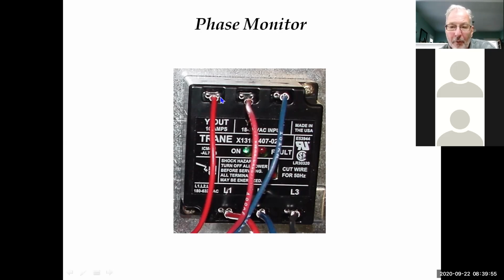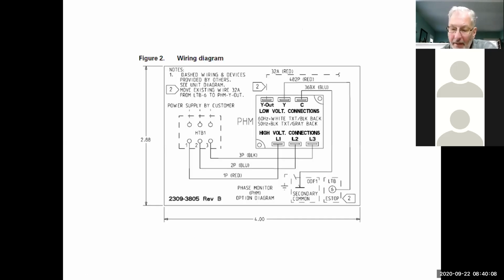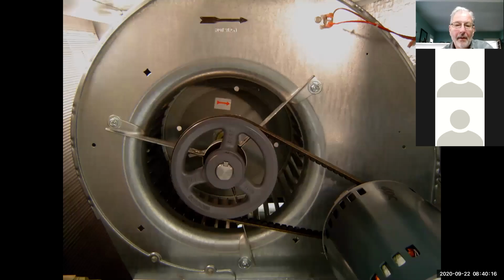Make sure you're getting 24 volts on this Y out. Here's your power, line 1, line 2, line 3. It's just monitoring power. Make sure you've got all three phases. Make sure they're phased properly. This is the internal connection to it. And again, we feed that by itself. We feed it from a separate circuit, okay?